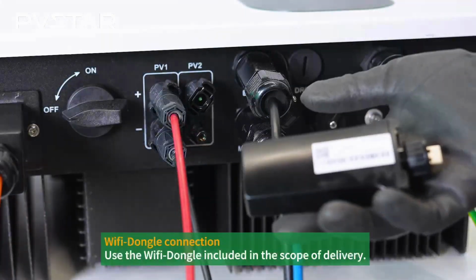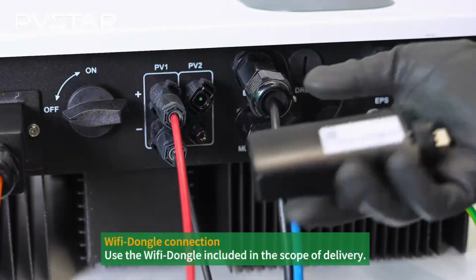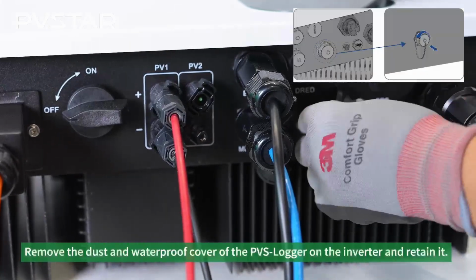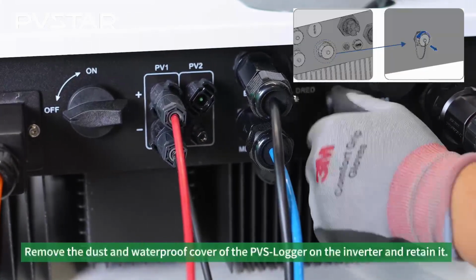In the next step, we will do the Wi-Fi dongle connection. Use the Wi-Fi dongle included in the scope of delivery. Remove the dust and waterproof cover of the PVS logger on the inverter, and retain it. Notice, rotating the communication modular will damage the communication modular. The communication modular is protected by locking nuts to protect the reliability of the connection. If the body of the communication modular is rotated, the communication modular will be damaged.